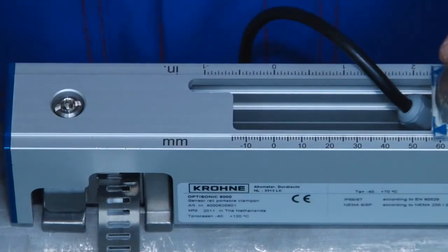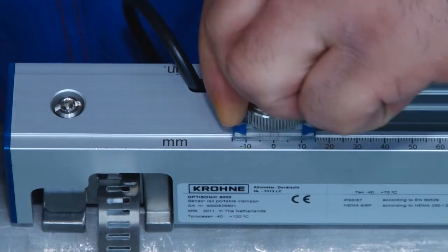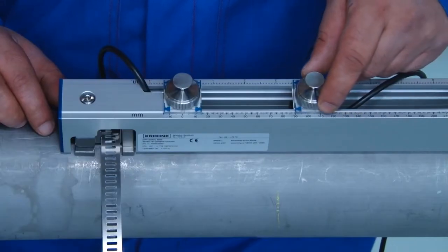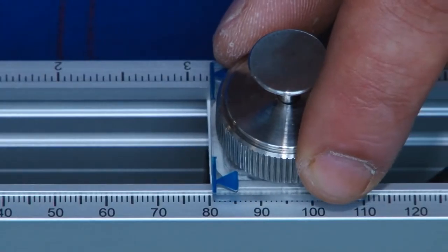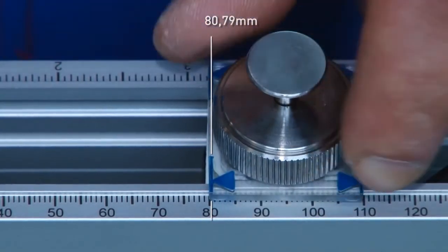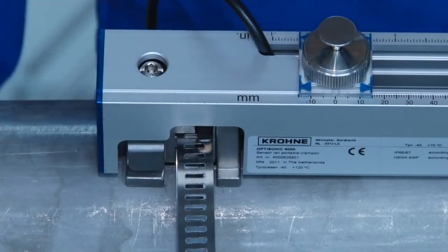Place the transducers at the correct distance. For this, put the down transducer on the zero position in the rail. The second transducer can now be placed accurately using the ruler on the rail. Take the contact grease from the tube and use the click and turn mechanism of the fixing units to apply the contact grease.